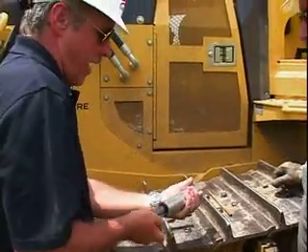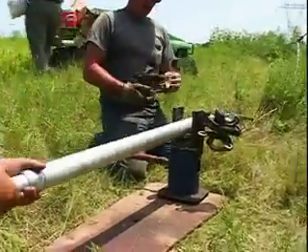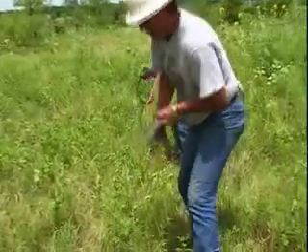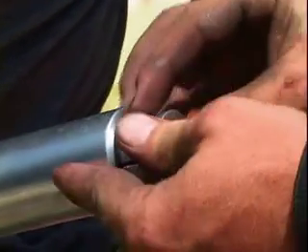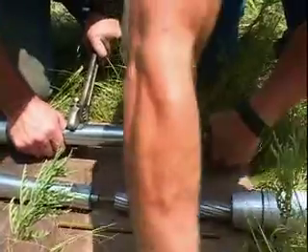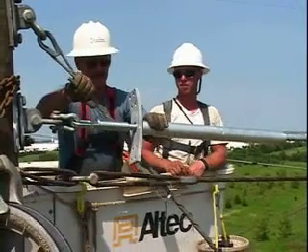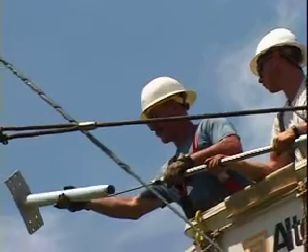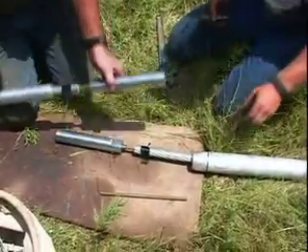We are interested in the connector technology — where we can crimp the cable and apply the wedges in a suitable manner that is in conjunction with standard practices for the industry for transmission lines. We had to develop a wedge type of technology and a mechanical pressure to complete the crimp on these connectors without impairing the integrity of the core itself. Later on today we will be pulling some cable through the blocks, installing dead ends on both ends, and also cutting in a splice to determine if the techniques are suitable.